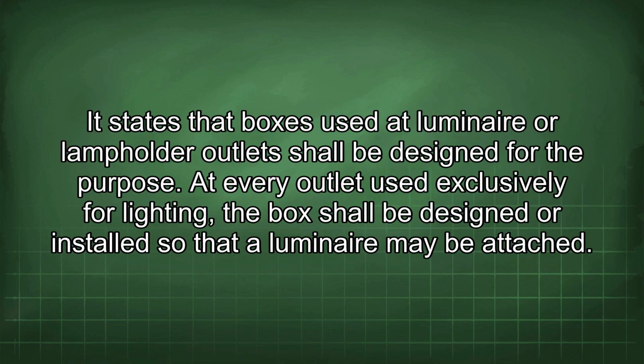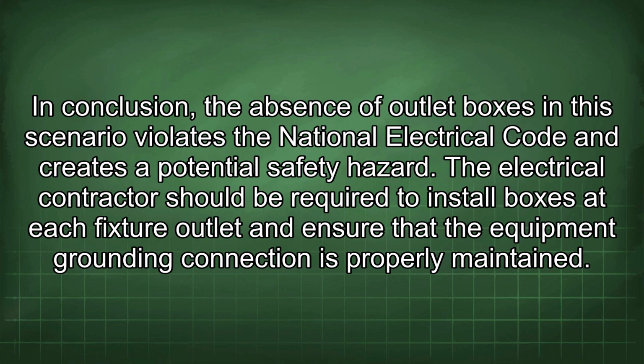It states that boxes used at luminaire or lampholder outlets shall be designed for the purpose. At every outlet used exclusively for lighting, the box shall be designed or installed so that a luminaire may be attached. In conclusion, the absence of outlet boxes in this scenario violates the National Electrical Code and creates a potential safety hazard. The electrical contractor should be required to install boxes at each fixture outlet and ensure that the equipment grounding connection is properly maintained.